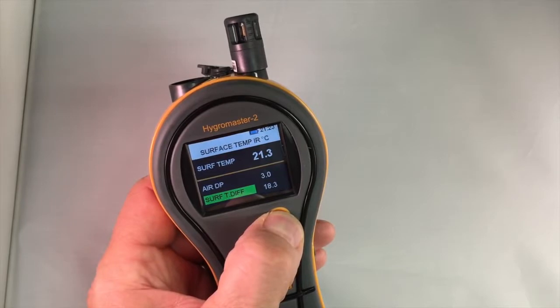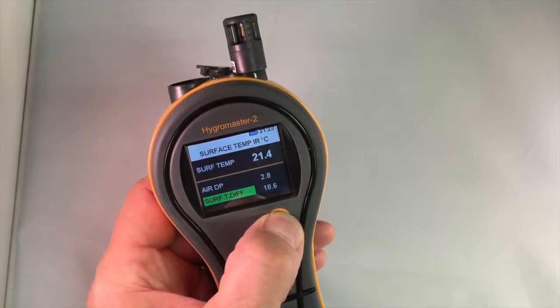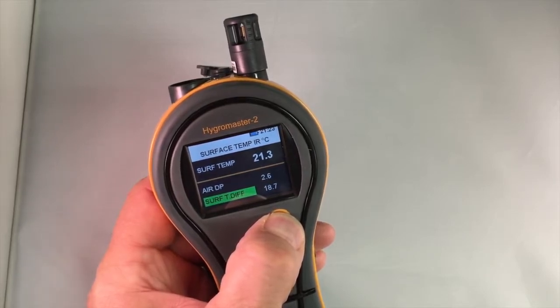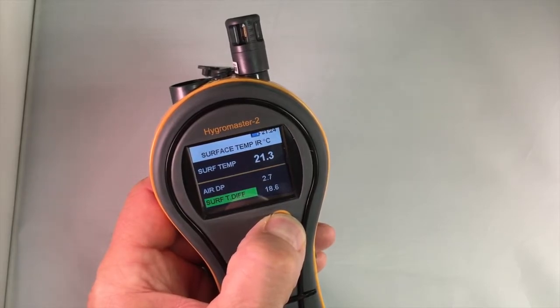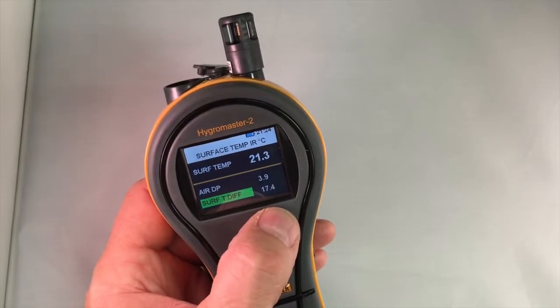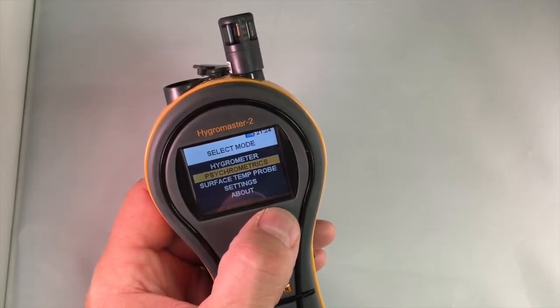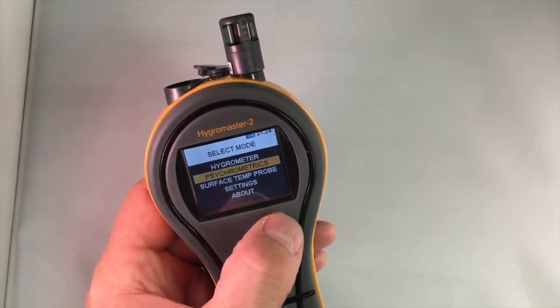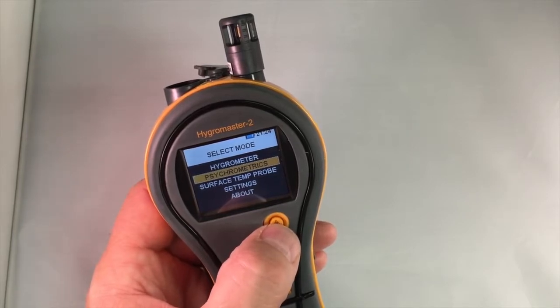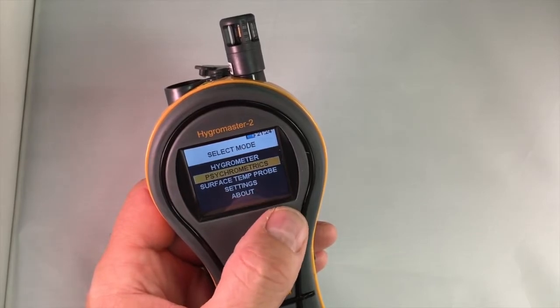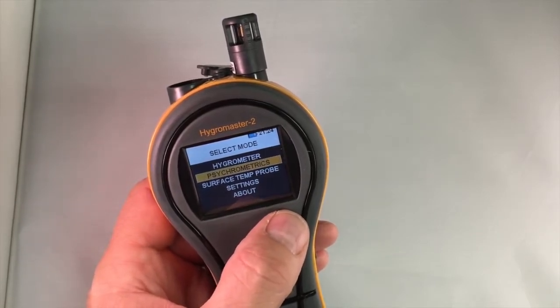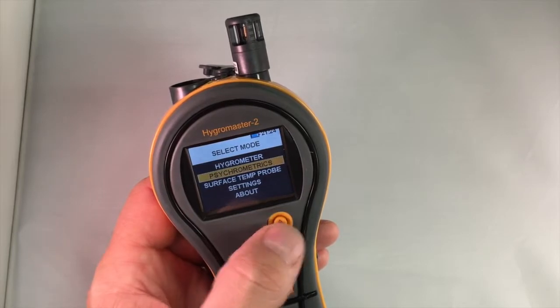As that number lowers to close to 0, the green signal turns to yellow, and once you hit dew point, it turns to red, meaning condensation is occurring. It takes the relative humidity and temperature of the room and the surface temperature and calculates the surface's proximity to dew point. We have a buzzer on here, so you can stand in the room and shine this at the wall, and when it finds condensation, it'll give you an audible warning as well. Very handy for finding condensation extremely quickly.